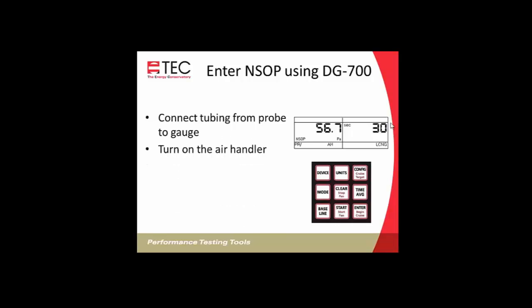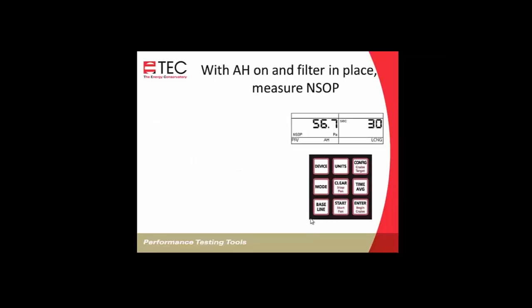We will turn on the air handler, set the DG700 to the pressure air handler mode. So we'll click our mode button on the DG700, and we'll keep pressing it until we toggle across pressure flow at 25, pressure flow at 50, etc., until we get to the PRAH mode. When we get to the PRAH mode, we're going to see NSOP flashing. Once that begins flashing, we will push the start button.